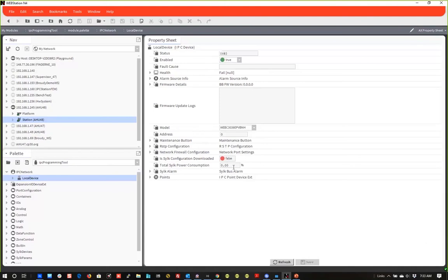Is it the same as a Spyder? In other words, the Sylk calculator. It's beefier, but you can only have 4 ZIOs. I think you could actually have 4 TR-75s on the network if you wanted. You could only have 1 on a Spyder. Still it's 4 max, and they didn't say whether TR-42s would be the same way. If it has humidity and carbon dioxide, they're going to consume more power. Right, not resources as much as power.